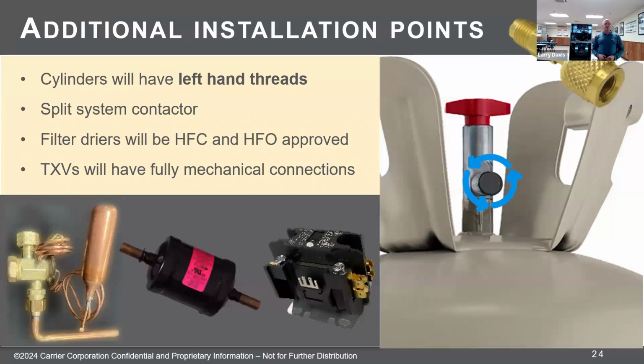What's different about some of the components? You'll see some of this repeated as well. Big difference on the refrigerant cylinders. The 454B refrigerant cylinders are going to have a left-hand thread on that fitting. So you will need to get that adapter that you see to adapt your standard hoses and gauges.